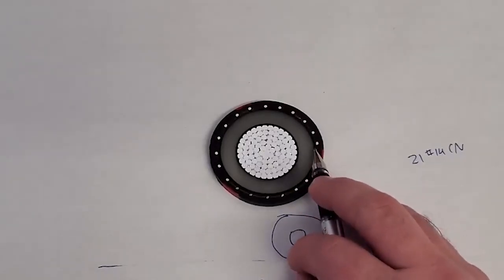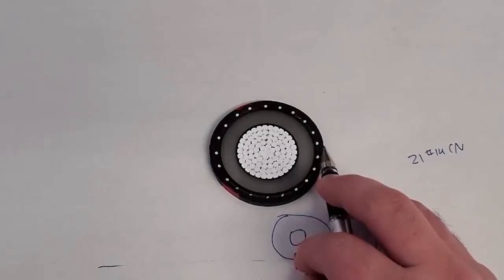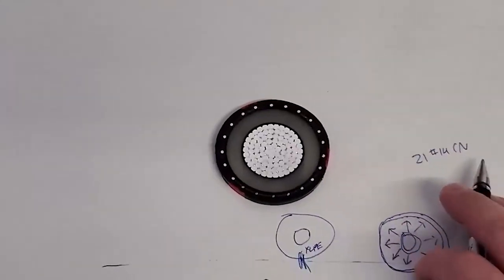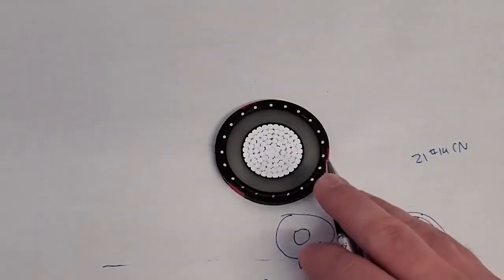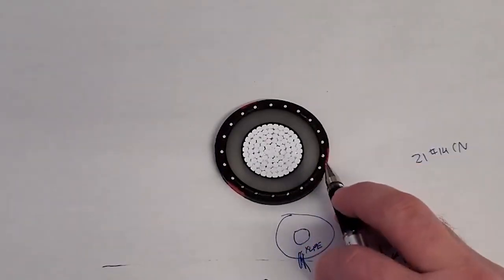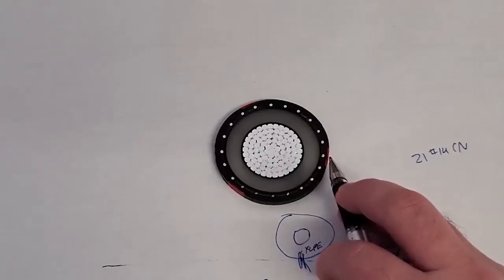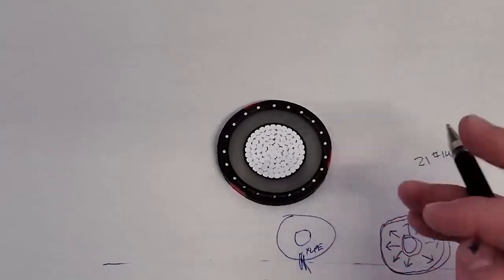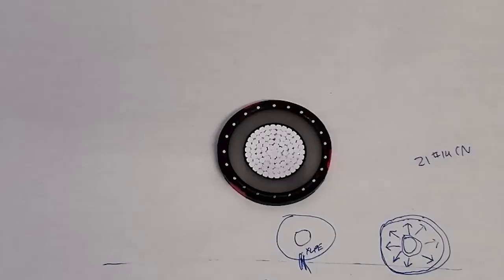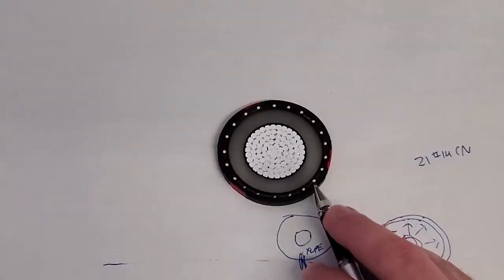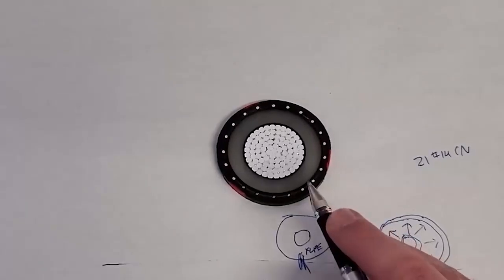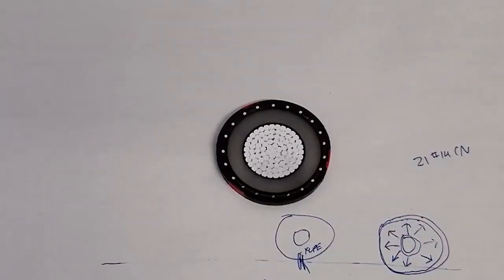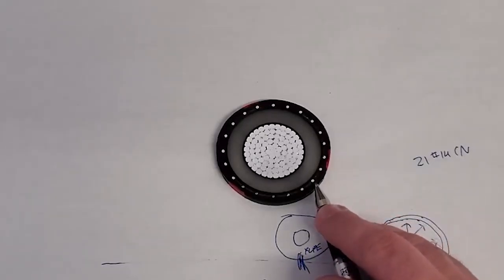So to help protect that insulation shield is this last layer, and that's the jacket. It serves no electrical function. It is simply there to protect the semicon and the cable from damage. That's all it does. It's extremely hard. You can actually try to take a knife to it and stab it. I doubt you're going to get through that layer. And this layer is either a PVC or an LLDPE layer. LLDPE is a little bit newer than the PVC, and it's better, in my opinion, because it's resistant to animals that like to bite and chew into things for whatever reason. They don't mind biting into the PVC, but they do mind eating into this LLDPE. They won't. It's also resistant to a wider amount of chemicals. Not that you're going to be spilling crazy chemicals on your cable, but it's just better having a slightly better and more resistant layer. So again, that's the LLDPE in this.